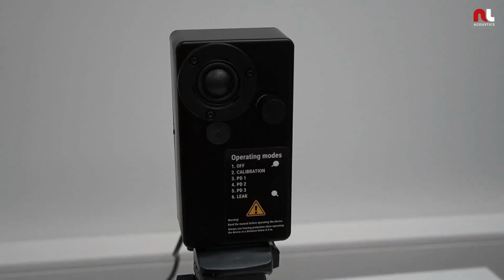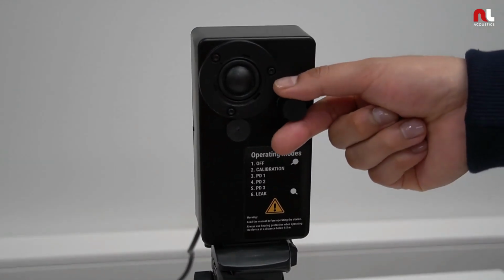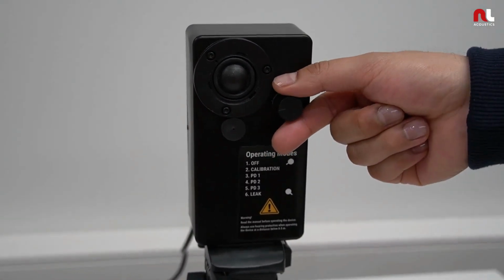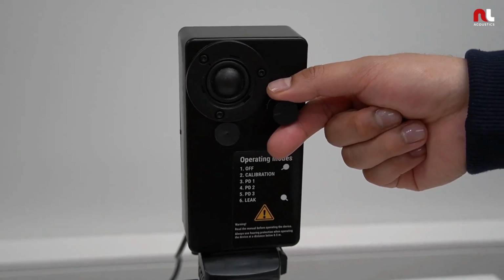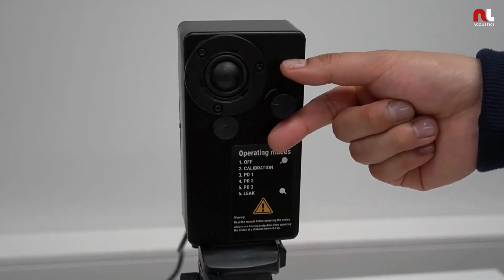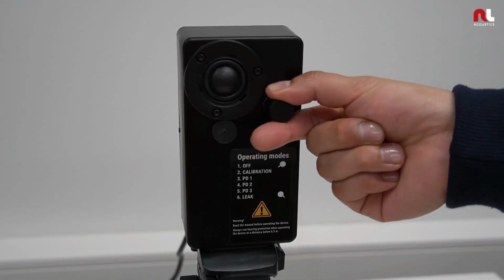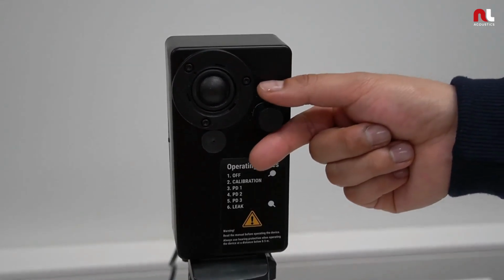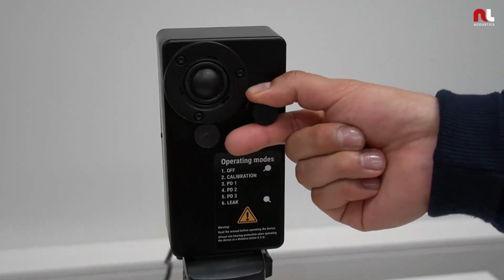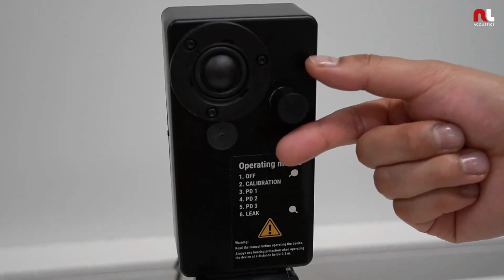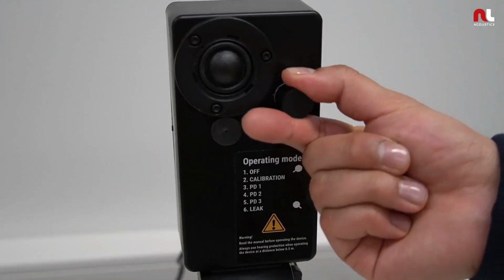When you turn on the NL Sonic Tester Multi, the first mode is the calibration mode. In the second mode, the Sonic Tester produces a corona discharge sound. The third one is a floating discharge, and the fourth a surface discharge sound. The last mode produces the sound of a compressed air leak.